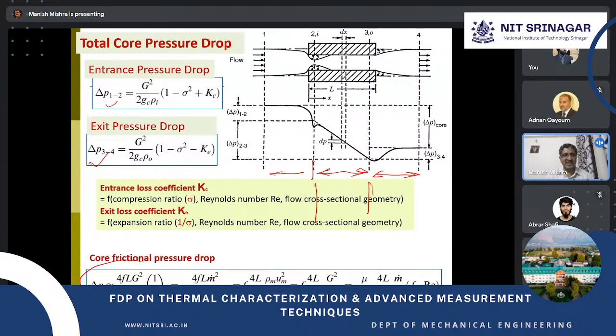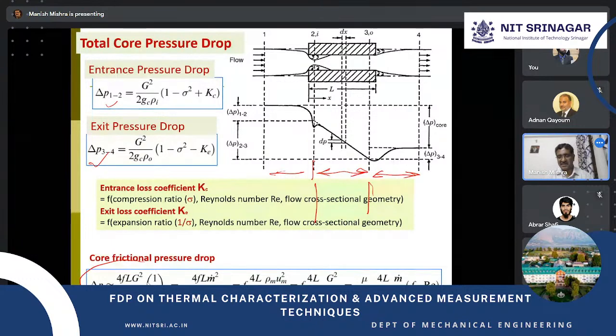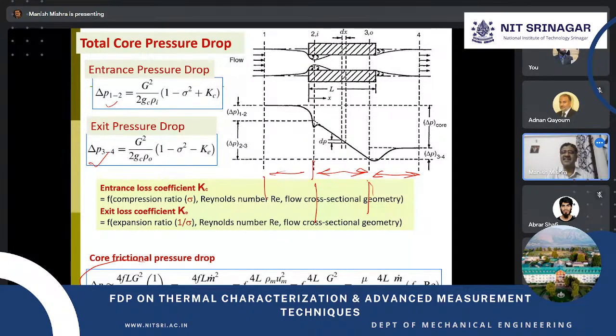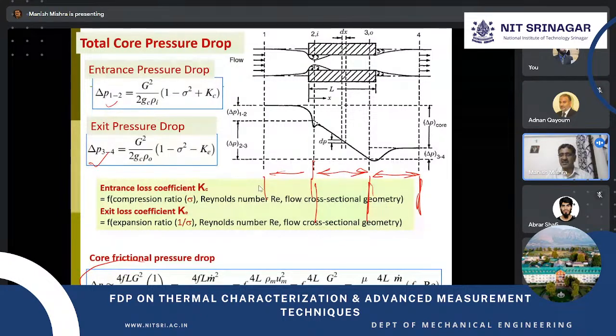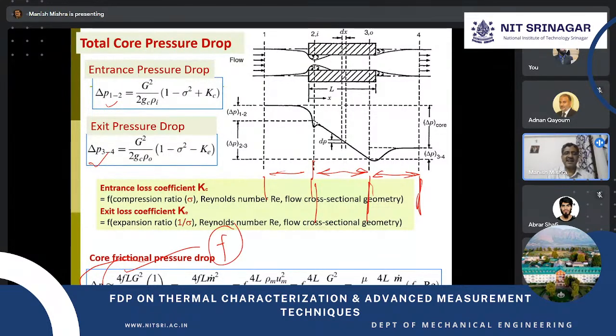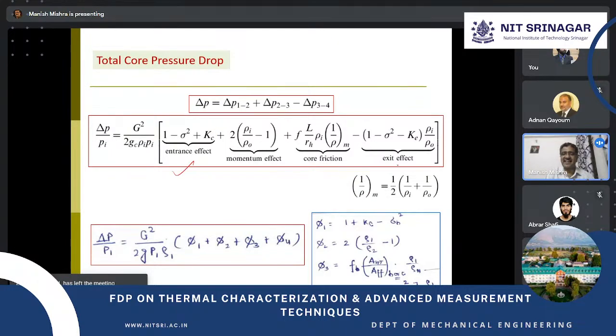It is 4FLG squared over 2 rho DH, something like that, provided I have a constant value of density and other properties. While gaseous flow passes through these compact passages, the effect of compressibility also comes into the picture, and if that is changing, we have to incorporate that aspect too. So the calculation of heat exchanger pressure drop, at a precision level, contains three major components, and summing up all of them gives the exact value of pressure drop. From there, equating that will give the value of F along with J, which gives the total characteristic: entrance, exit, core friction, plus momentum and compressibility effects.